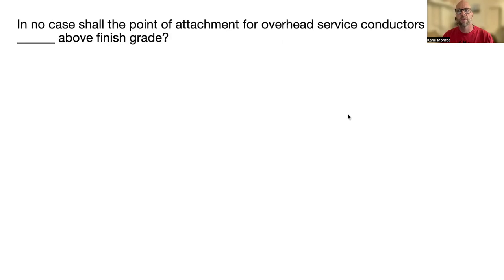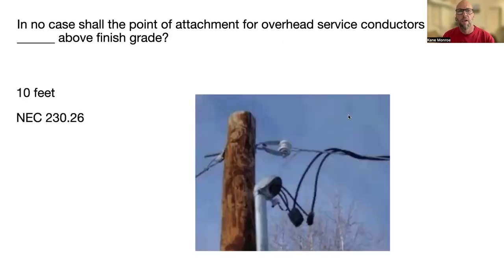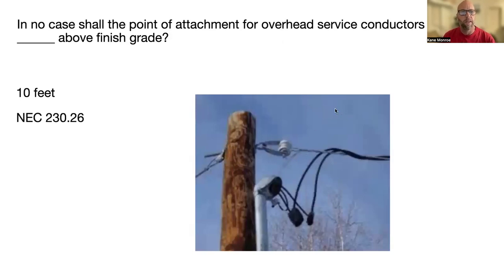In no case shall the point of attachment of overhead service conductors be less than blank feet above the finished grade — and that's 10 feet, NEC 230.26. This attachment point shall not be lower than 10 feet.